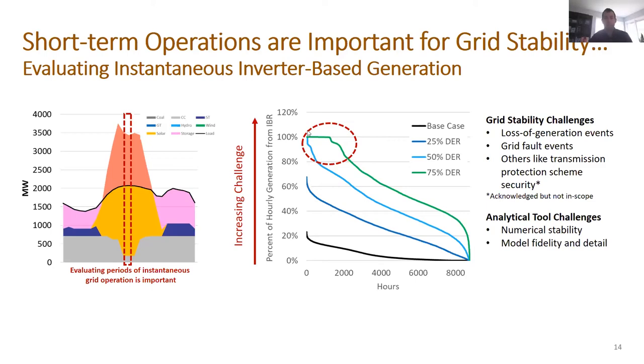Hi, thanks, Derek. And just to pick up on this slide here, the grid stability challenges that we're looking at are dynamic events that happen over the course of a few seconds. And it looks to say, if there's a large disturbance on the grid, how does the grid recover from that? And also a note, given that we are pushing the grid and modeling the grid into very high levels of renewable penetration, places where few grids have gone before and where studies are still being worked out, there are also tool challenges in addition to the real world challenges of making a system work like that. And so I think it's important to acknowledge that not only are we challenged in terms of getting the system to work, but we're also challenged in terms of studying the system and to be cognizant of that. So on the next slide, we'll get into the different types of dynamic disturbances we looked at.